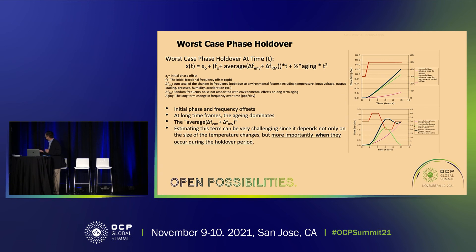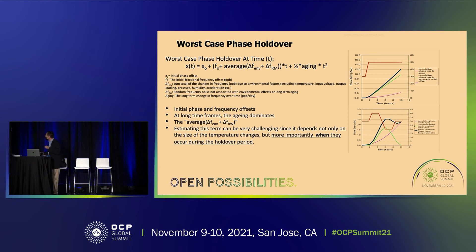This graph shows some unpredictable behavior during holdover — just as an example. The top curve shows temperature. During the initial stage, there's an error increase, but after a certain time the oscillator becomes quite stable with temperature change. With temperature variation, the error may even reduce. This illustrates how those factors impact holdover capacity in a nonlinear way.